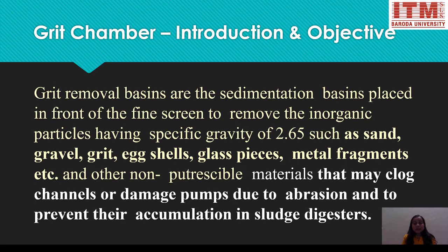The grit chamber is basically a settling tank. Grit removal basins are sedimentation basins placed in front of the screen to remove inorganic particles having a specific gravity of 2.65 — more than water — such as sand, gravel, grit, egg shell, glass pieces, and metal fragments. They also remove non-putrescible material that may clog channels or damage pumps due to abrasion, and prevent their accumulation in the sludge digester.